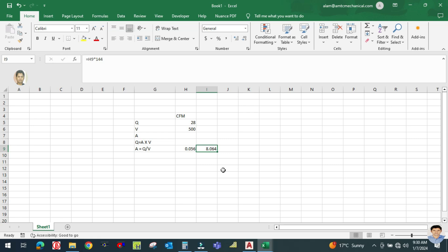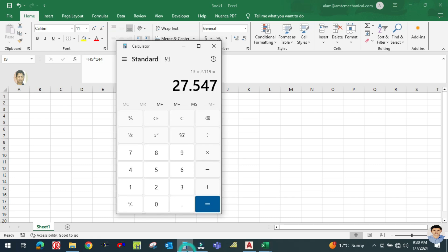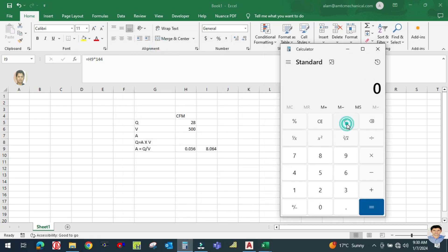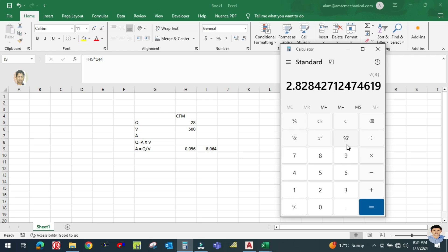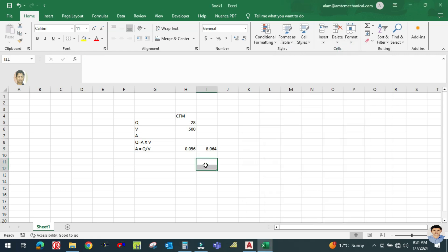Taking the square root of 8 square inches gives approximately 2.8 inches, which rounds up to 3 inches. However, 3 inches is not available as a standard size, so you have to go for 6 inches. The minimum diffuser size will be 6 inches.